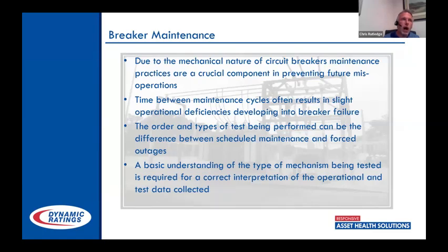It's these slow-operating breakers that get overlooked a lot through testing. Anyone who's done any amount of breaker testing knows that once you operate a circuit breaker, the timing of that breaker improves greatly. For a long period of time, all the testing we did on breakers was done after the breaker had been taken offline — timing and travel type testing — which requires an opening of the breaker, drops to be removed, grounding put in place. After you've operated that breaker the first time, that second operation can be very deceiving as to what the breaker is actually going to perform like in a real-world circumstance.